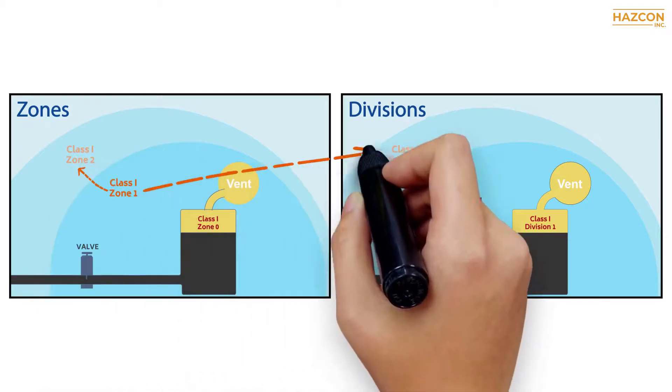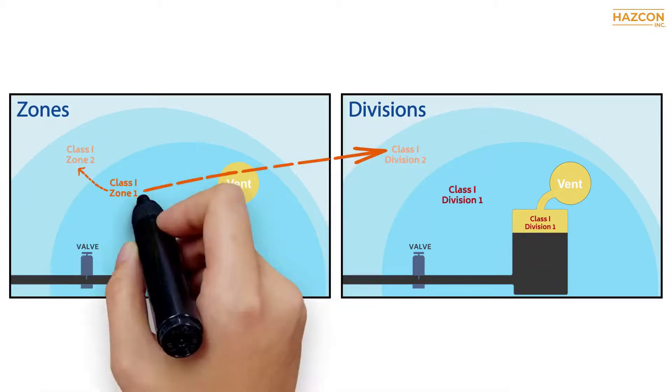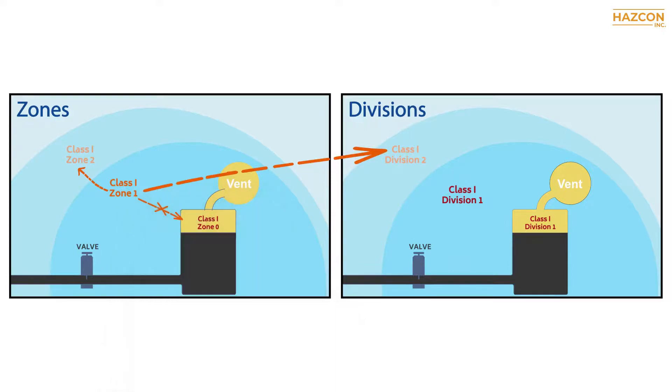Zone 1 products may be installed in zone 2 and Division 2 only. Please note that zone 1 products may not be installed in zone 0 or class 1 Division 1.